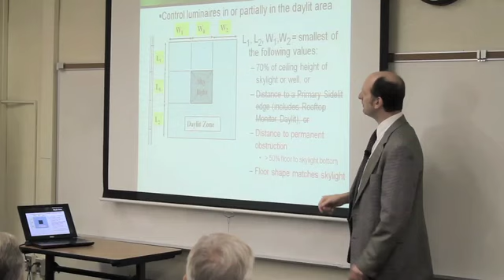We'll talk a little bit about daylighting. So in daylighting, we've got the 3 basic different lighting zones. The first one is if I've got a skylight, I draw the daylit area around the skylight, and the rule for the engineer is that they figure out 70% of the floor to ceiling height on each side. That gives you your daylit zone. There used to be a rule that said if you had a window and it overlapped with the skylight zone, the window zone would win. They've changed that and said now the skylight zone wins if there's any overlap.